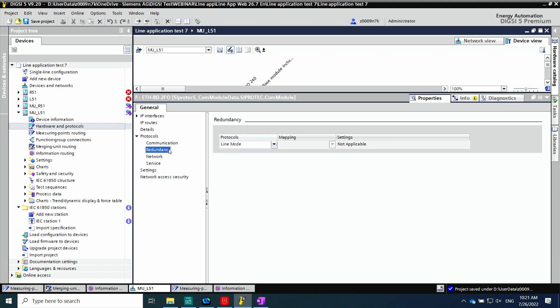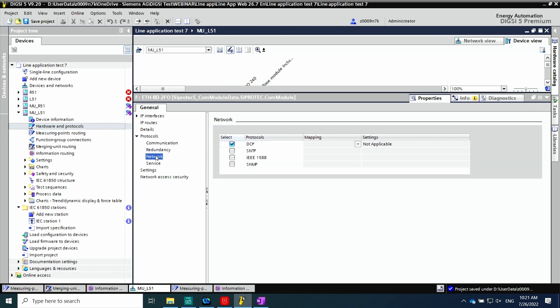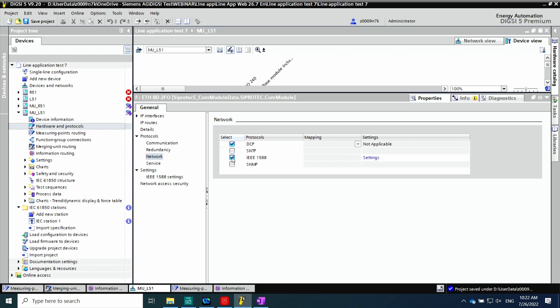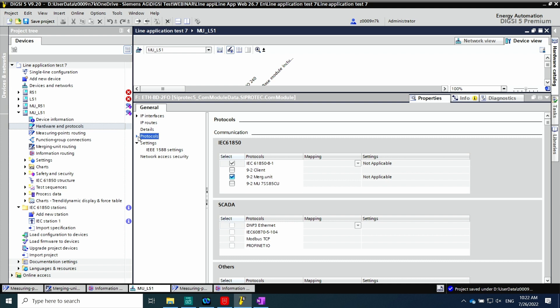For redundancy purposes, we can select the redundancy protocol for the communication network. We have line mode, RSTP, PRP, and HSR. HSR and PRP are recommended for process bus networks. We need the IEEE 1588 protocol, which is necessary to synchronize the process bus network. We require the sample synchronization that is done here in the network settings.